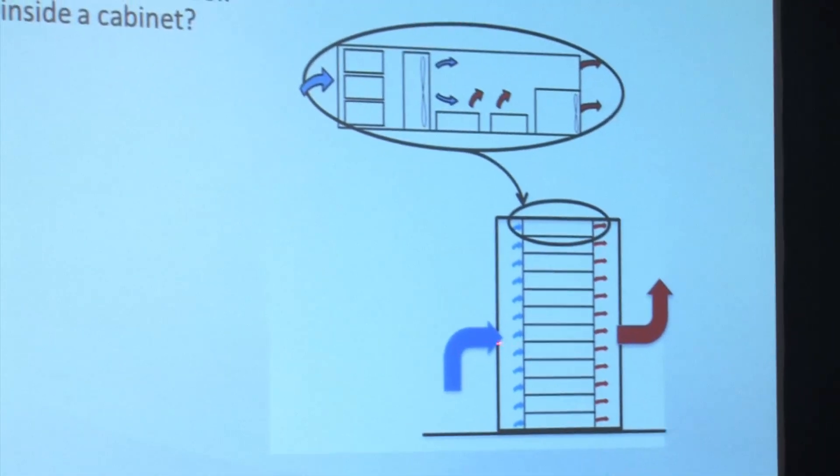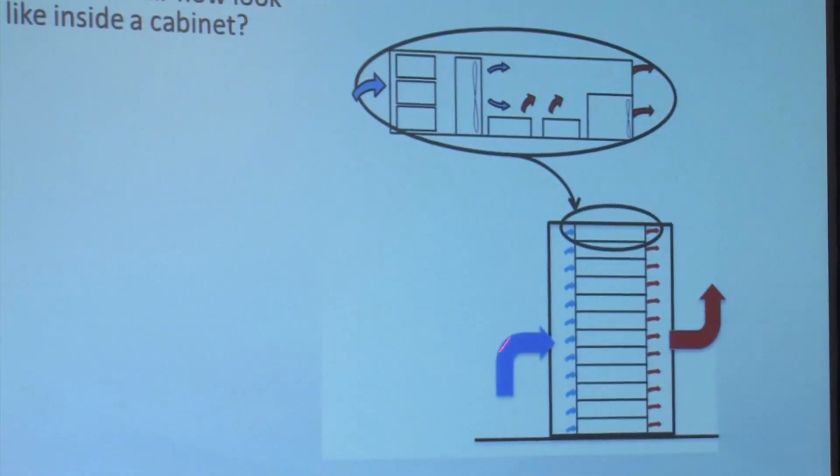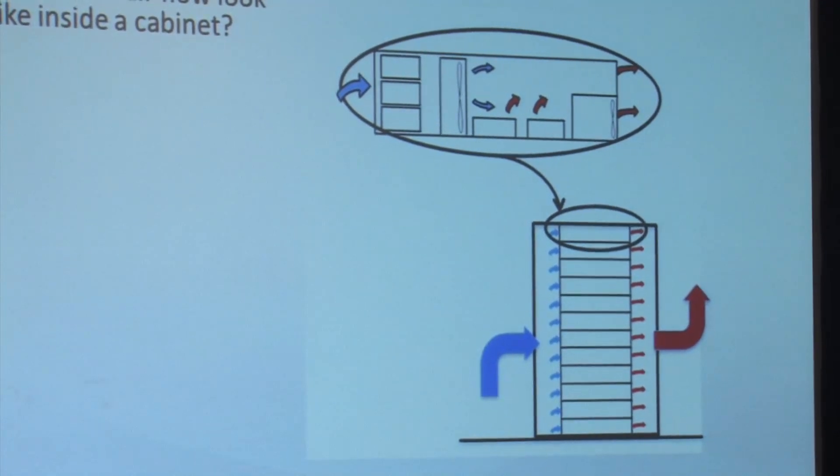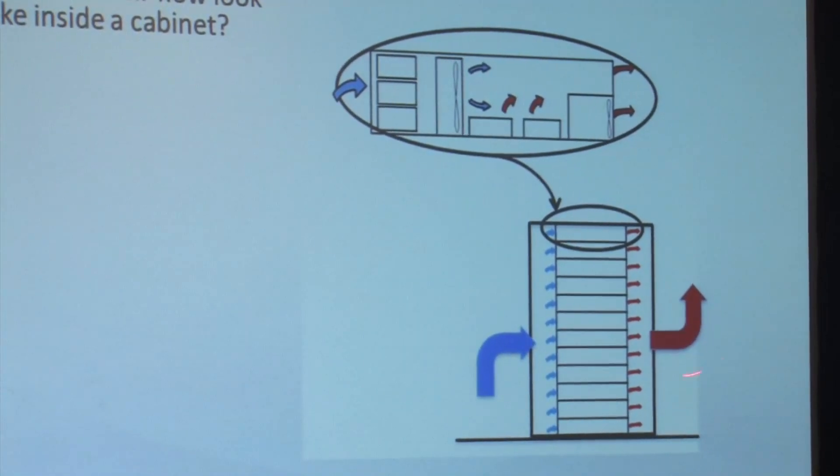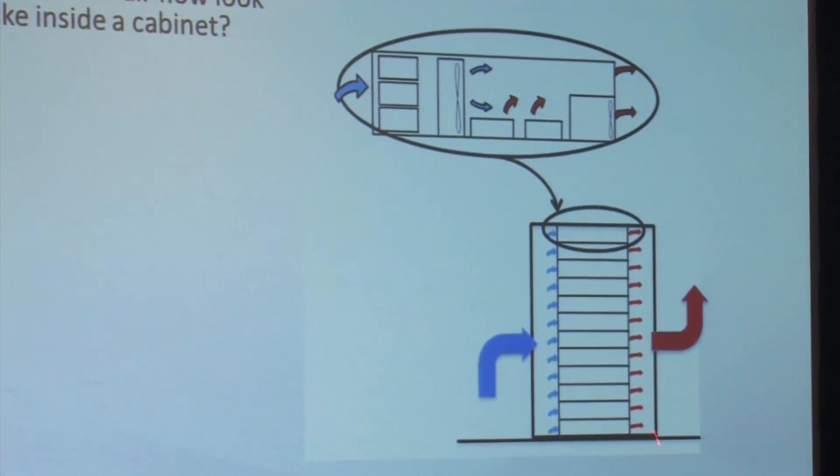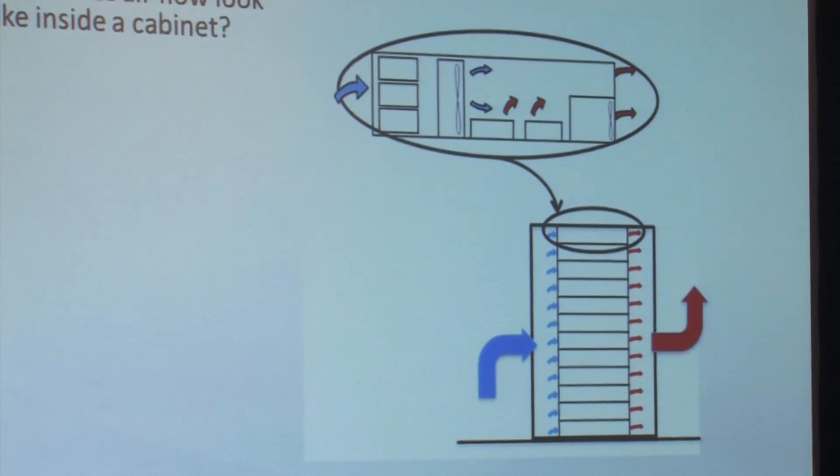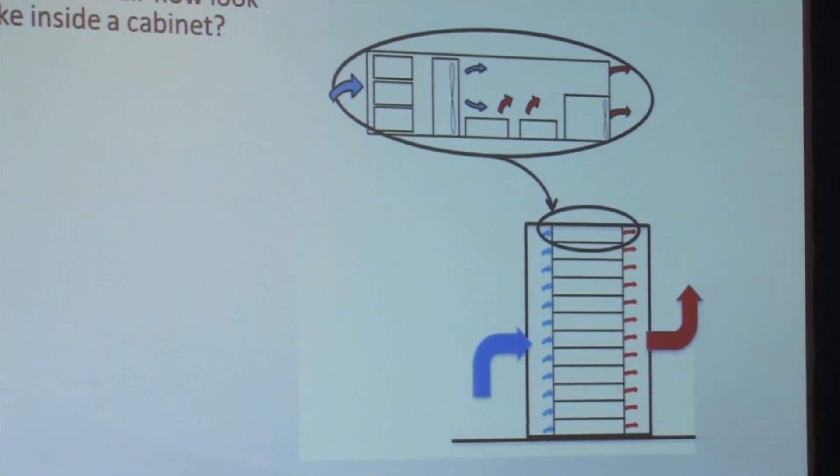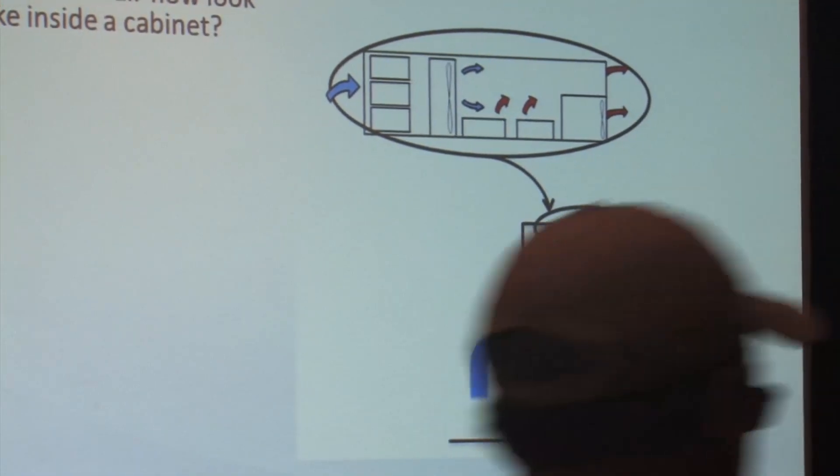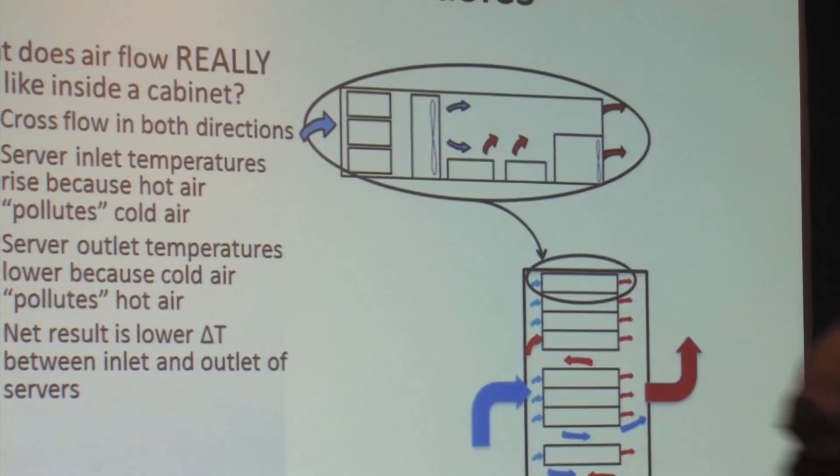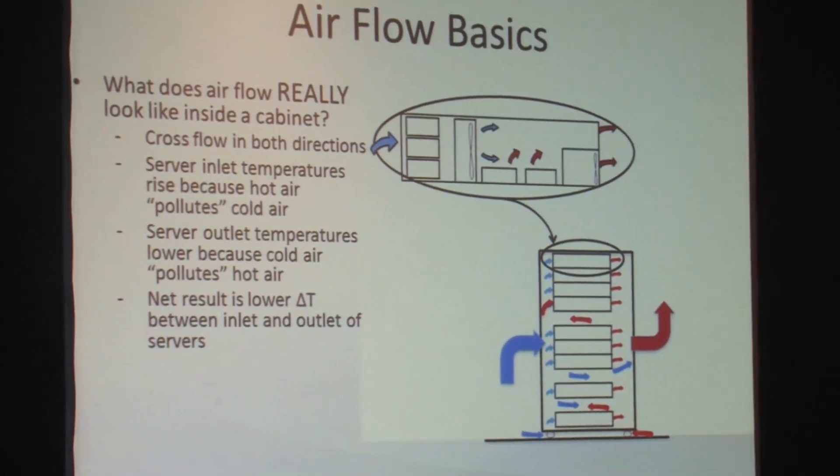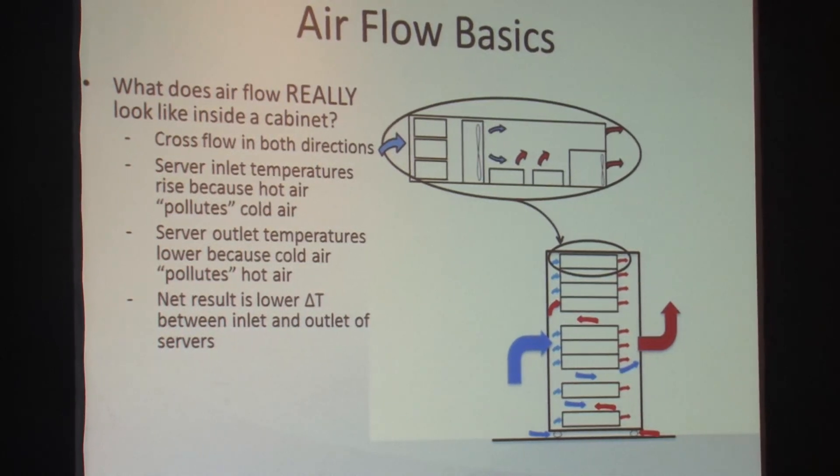So you take that box and put it in the cabinet. So now, with its own little airflow, which now I've migrated into a stacked-up cabinet, everything is perfect. Here's my temperature in at the supply air temperature. And here's kind of the average of all of the outs, because they may all be different. And as you can see, I've got good airflow here. But that's not really what happens in most boxes. It's not what really happens in most cabinets.